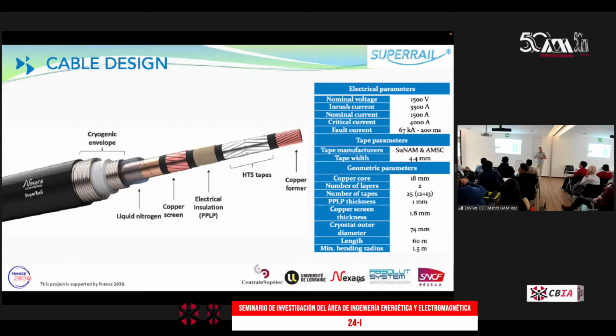I'll show you later a different picture. What is specific here is this part, the copper. In conventional normal operation of a superconducting cable, you don't need copper because the current goes through the superconducting material. But here, since we need to reach this high short circuit current, 67 kiloamps, you need copper, because with these high currents, the resistance of the superconductor will be too high, so the current will flow through the copper core in the center. So this part is only designed to sustain the short circuit currents and avoid any heat in the cable itself.